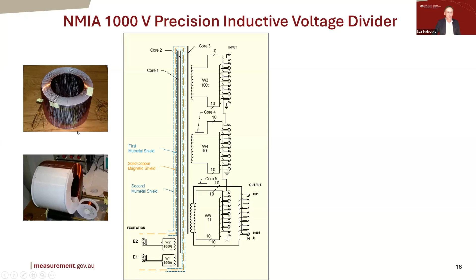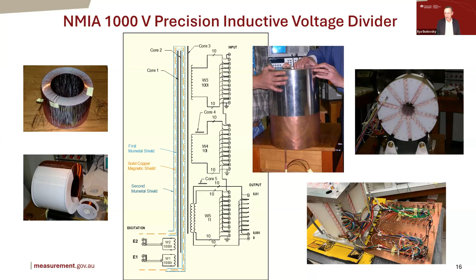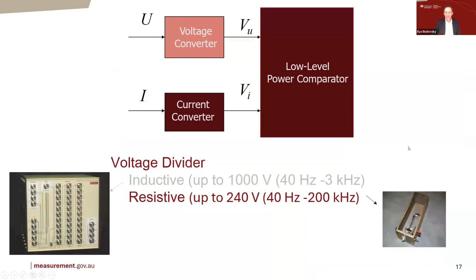What you can do is put another winding on it, shown here, and then a magnetic screen, the best being a combination of copper and mumetal, and then your defining winding. This is really a combination of 3 transformers, because the flux in the second core is only responsible for compensating the error in the first stage, and the flux in the third core compensates the error in the first two. So if you have 3 transformers, each accurate to 0.1%, that's how you get a transformer accurate to 1 part per billion.